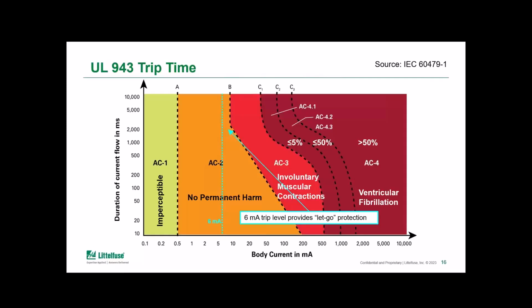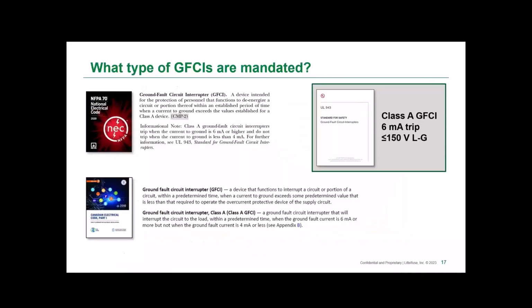And if the current is above the let go threshold, that means when the current is running through your body or your hand, it may cause the muscles to tense and you may not be able to physically let go. So when the UL 943 standard was designed, that value of 6 milliamps was selected on purpose, to be below that threshold.